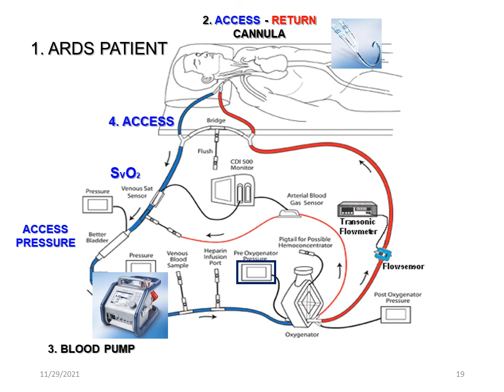It's negative. Then you've got the membrane oxygenator, which has got two pressures that are being monitored, transmembrane pressures, pre and post. And it has an oxygen sensor as well. Then you've got the return, flow and air detector. You've got the heat exchanger to warm the blood back to the patient's pre-extraction temperature, so the patient doesn't become hypothermic. It's returned to the patient via the bicaval cannula. This is your SaO2.